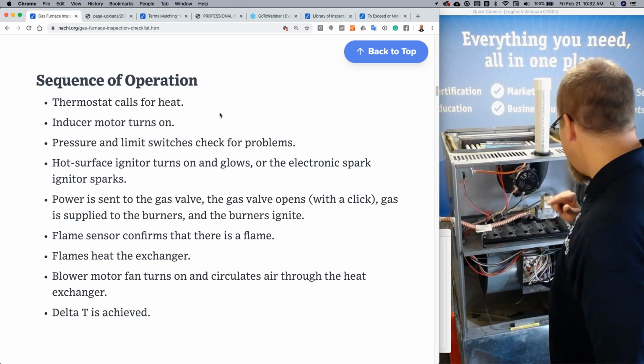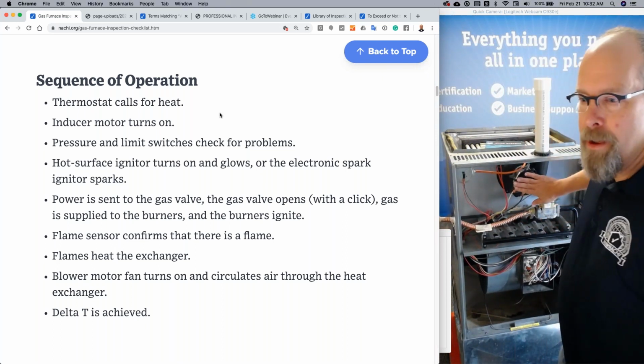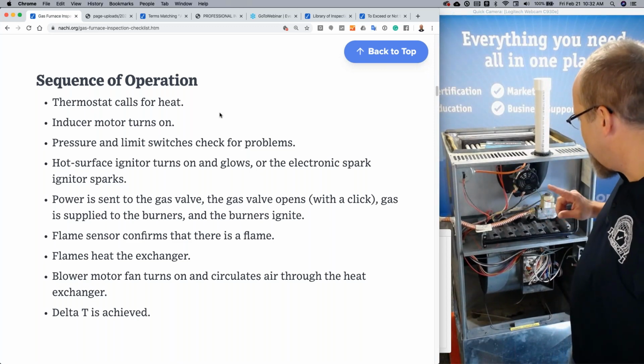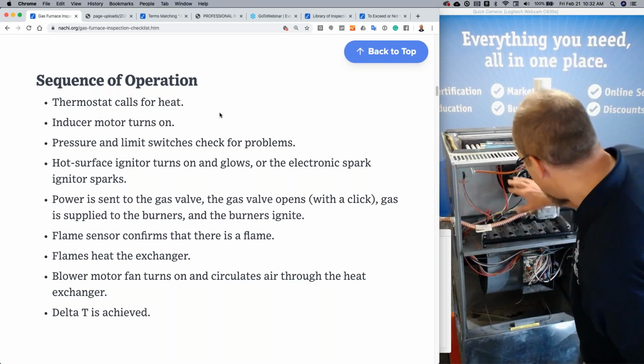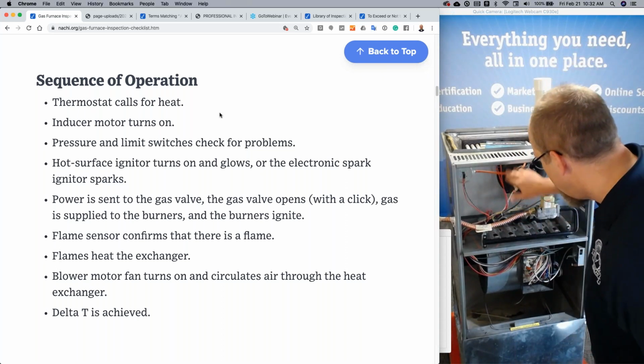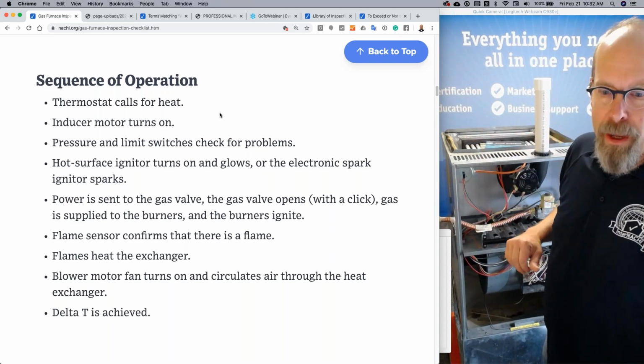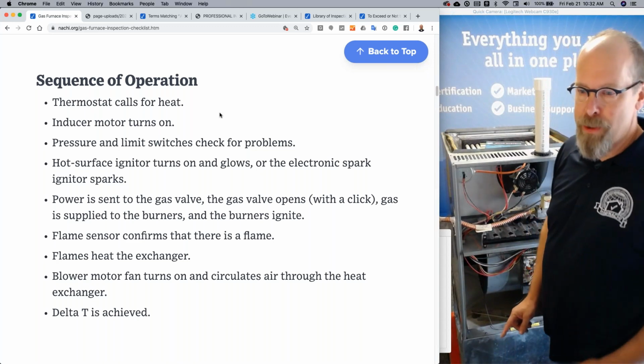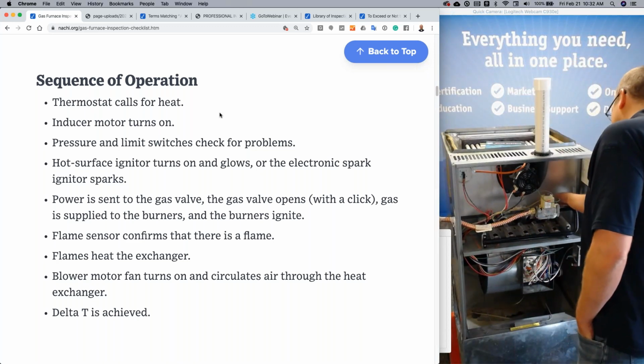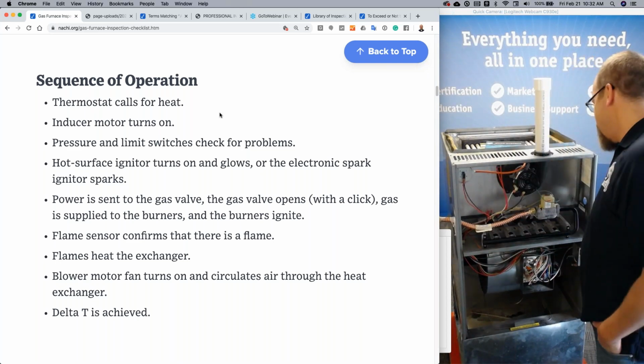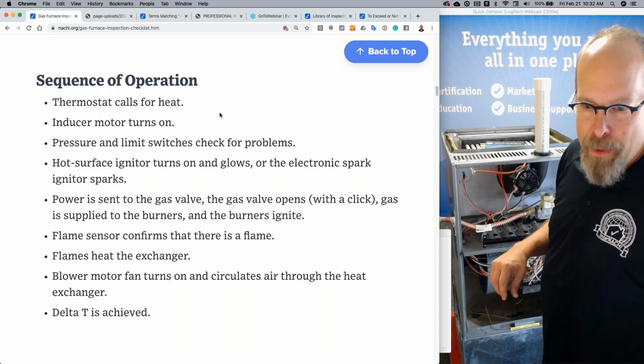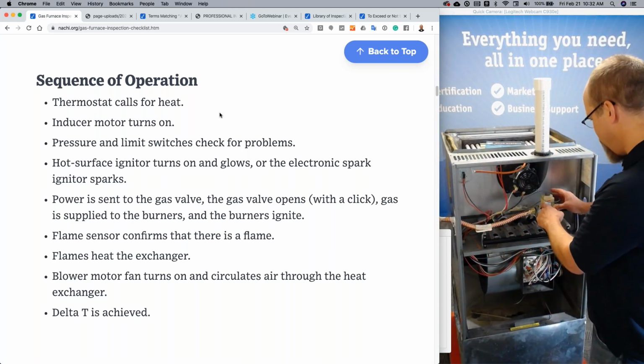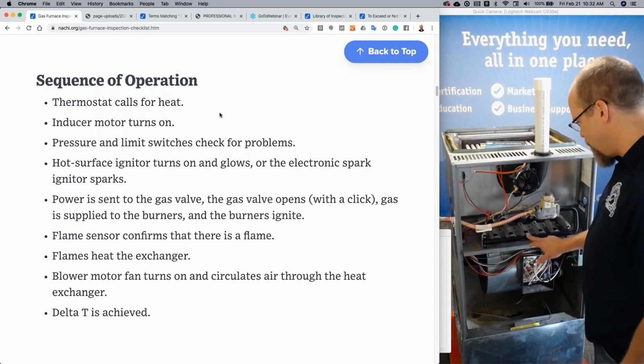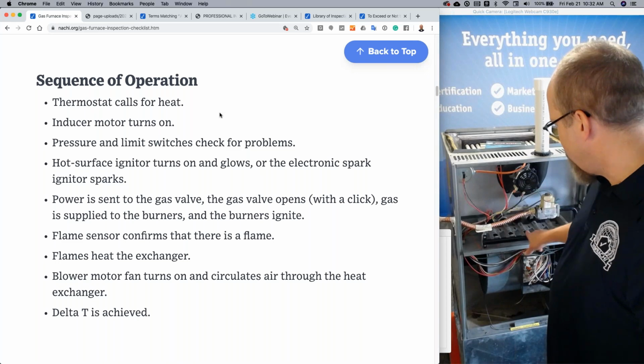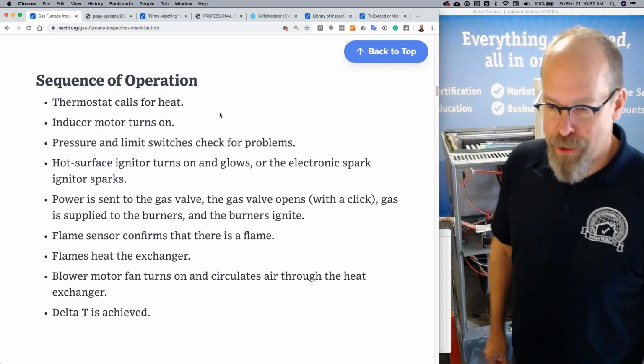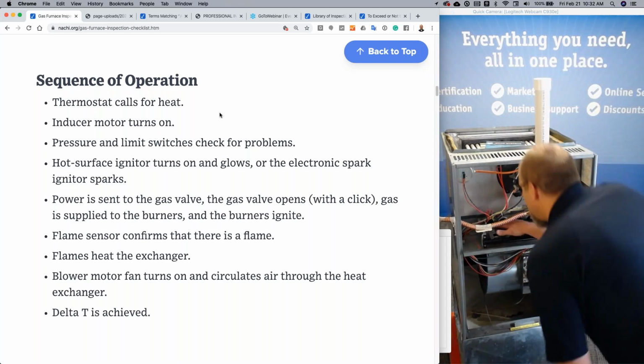And then the draft inducer fan, that's this fella right here, turns on. The pressure and limit switches check for problems, and we have one pressure sensor, there's the diaphragm there, and we've got a temperature limit switch there. The hot surface igniter turns on and glows, or there's a spark that can tick, tick, tick. Looks like I've got a stick here, and it'll glow red hot. The power is sent to the gas valve, and the gas valve opens up, it activates. Gas goes through the manifold into the burner ports, shots here, and ignites. The flame sensor confirms that there's flame, so there's that little stick there.